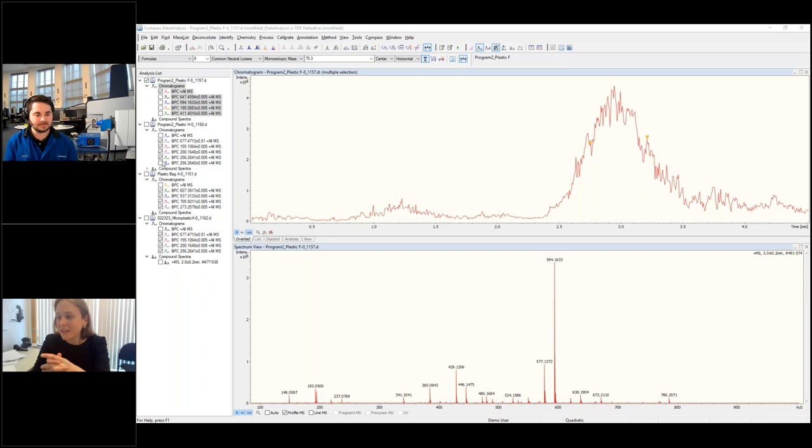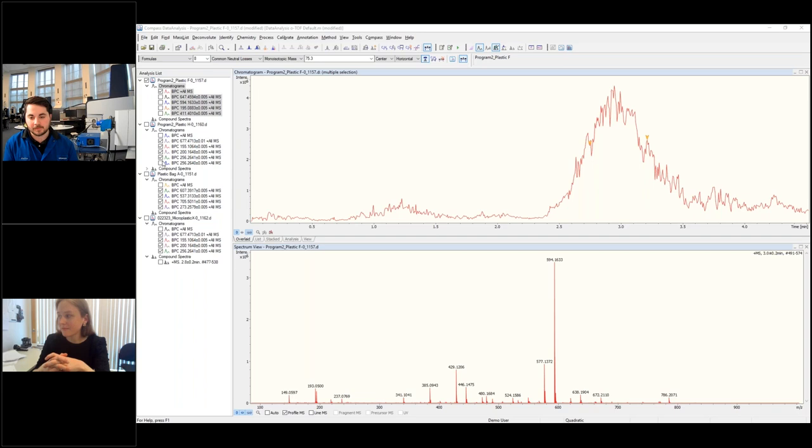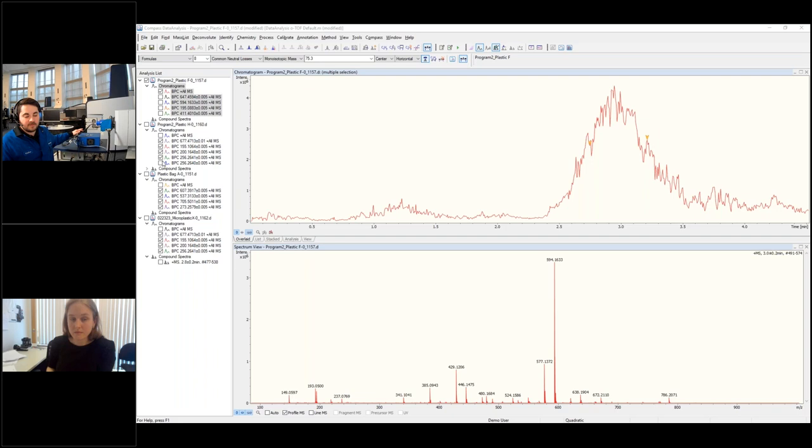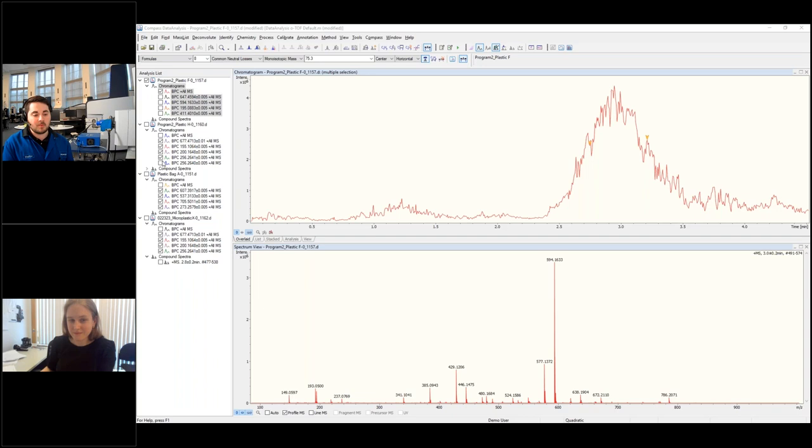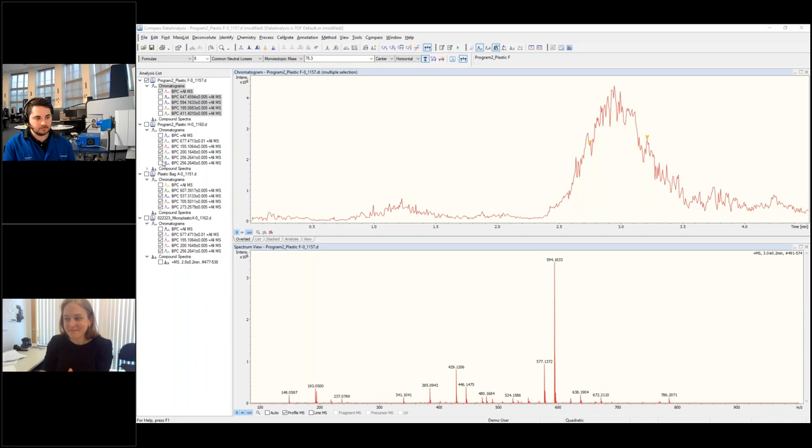Next question. Since you're using helium as the ionization gas, how much is actually used? That's always a big question for DART. Helium is becoming a hotter and hotter topic as it's becoming more scarce. And I forgot to mention the box in front of the DART is the controller for the powering gases. So the gas is actually regulated down to 3.2 liters a minute. And as you saw, we are running about a five-minute run. So you can toggle, go back to nitrogen once you're done with the run. But to kind of give you guys an example, I have a standard helium tank sitting next to the instrument and this has lasted me well over close to two months, two and a half months now. So the ion rocket does require helium, but it's a very small flow. So one tank can really last you quite some time.